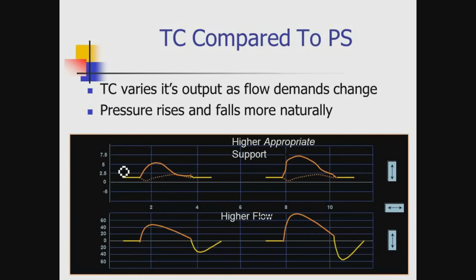So here I have a pressure level that's being generated for that inspiratory flow rate. And again, this is being done throughout the breath. It's altering this pressure level. If the patient wants more breath, wants a deeper breath, because remember, it's a pressure-based breath, they can take whatever volume and flow they want. At a higher flow, it kicks the pressure up to overcome that. So it's matching the patient during the breath on a breath-by-breath basis.